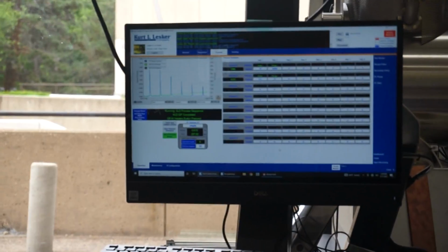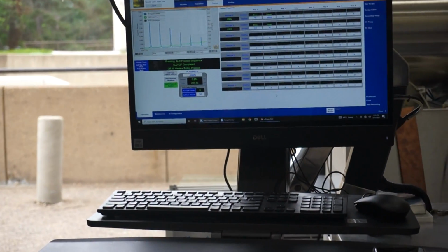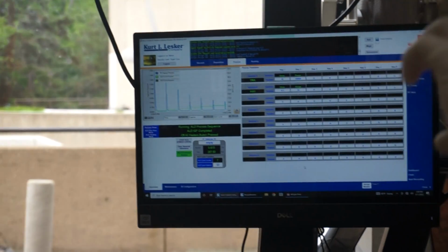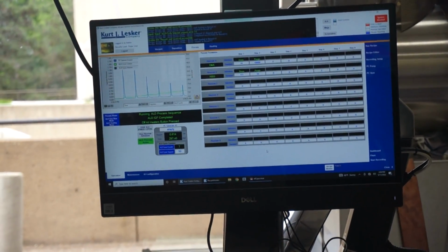I've got water. Matter of fact, what we'll do is at some point tomorrow, we'll do the pump purge, which you have to do. Take this ampule off, because I'm going to take it back anyway. And we'll put the other one back on, and we'll go ahead and do the pump purge again and do the conditioning recipe since we'll have atmosphere on that. That'll be good exercise.